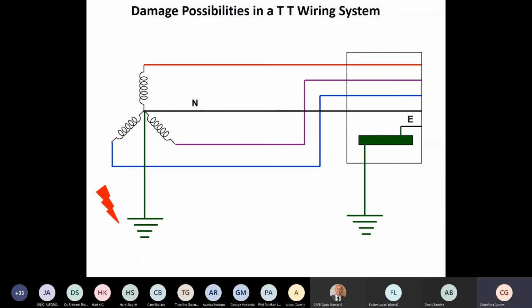There's another way of having lightning damage. Say, for example, if you get a lightning very close to the transformer earthing, or imagine that lightning current hits the medium voltage side of the transformer, and the lightning current passes into the earth through the surge protectors, and then the area around will have a high potential rise, especially if the earthing system is not that good. And then you're having low potential at the other side at the building, so the current will flow like that, and there will be again an arcing, usually at the main panel, sub panel, or at an equipment in the building. And the same thing can happen in this way as well.